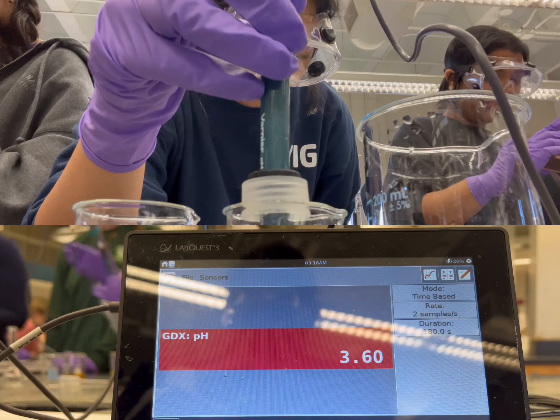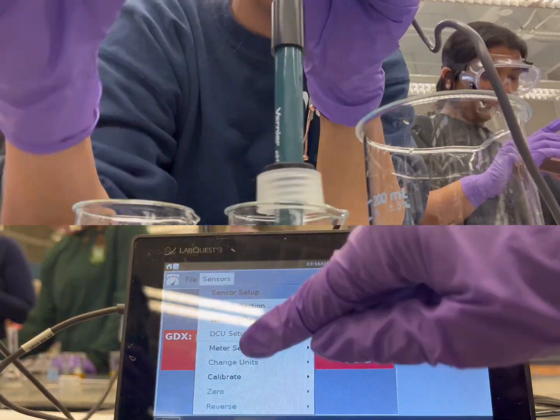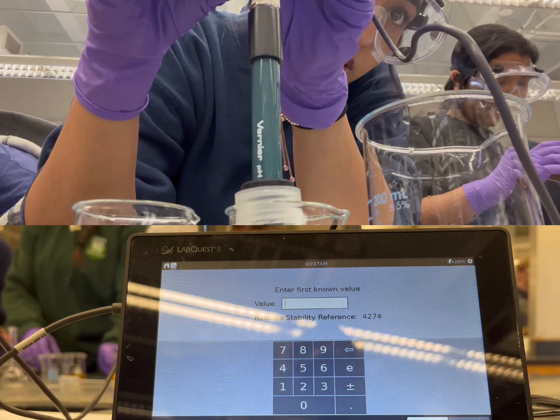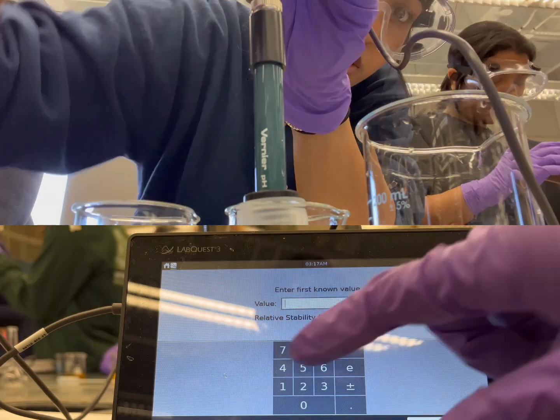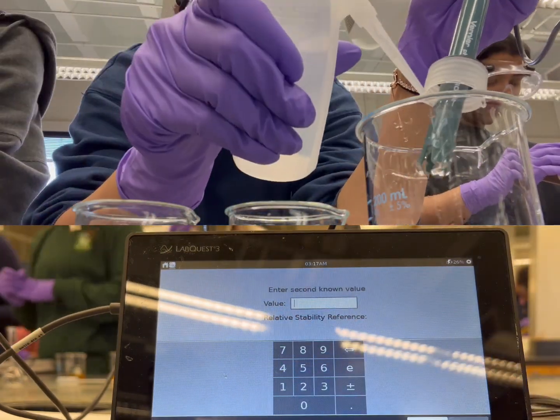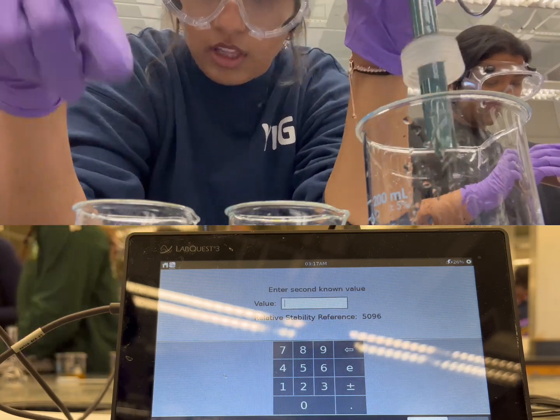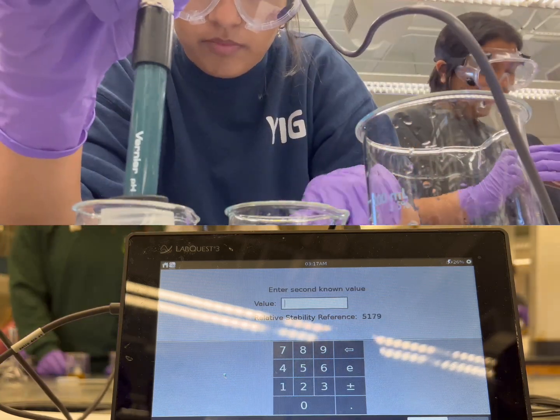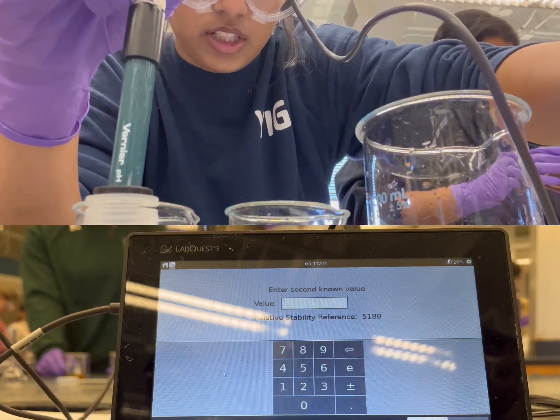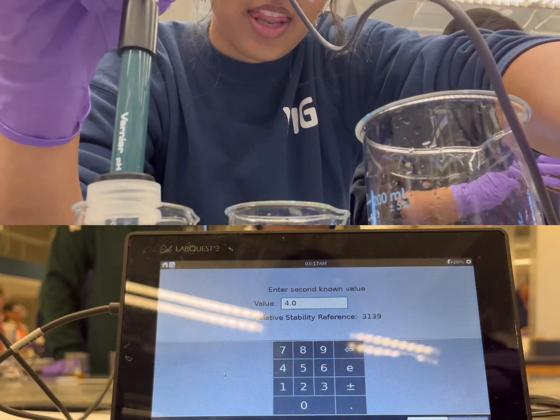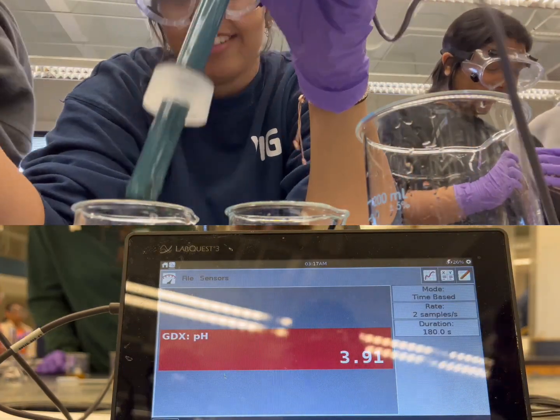First, we rinse the probe with distilled water to avoid contamination between solutions. Then we put the probe into the pH 7 buffer solution and register it. Then we rinse the probe again and place it into the pH 4.0 buffer solution, and after that stabilizes, we calibrate the meter to read 4.0. This ensures that the meter can accurately measure acidic solutions as well.